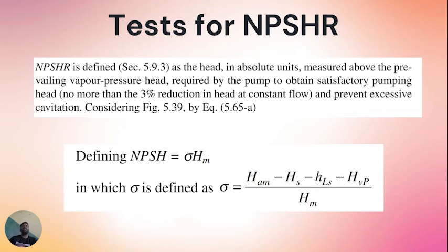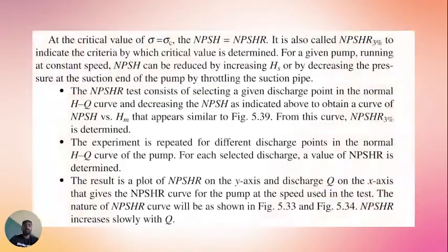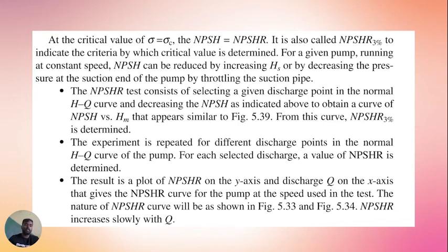NPSHR is defined as the head in absolute units measured above the prevailing vapor pressure head required by the pump to obtain satisfactory pumping — not more than three percent reduction in head at constant flow — and to prevent excessive cavitation. At the critical value of sigma, NPSH equals NPSHR, also called NPSH3 to indicate the criteria by which the critical value is determined. For a given pump at constant speed, NPSH can be reduced by increasing Hs or by decreasing pressure at the suction end by throttling the suction pipe. The NPSHR test involves selecting a discharge point on the normal HQ curve and decreasing NPSH to obtain a curve of NPSH versus head, from which NPSH at three percent reduction is determined. Thank you.